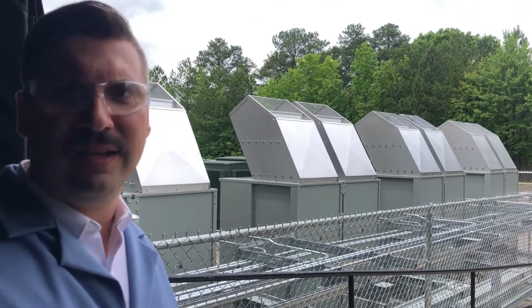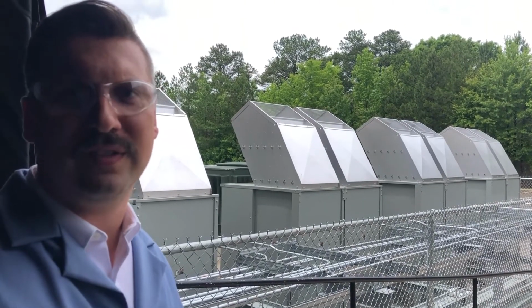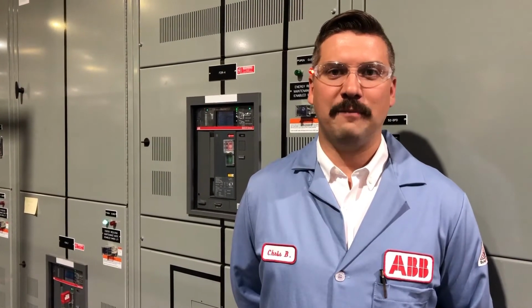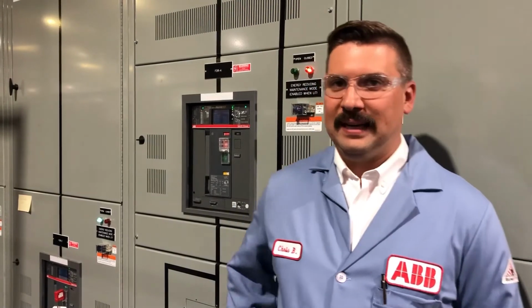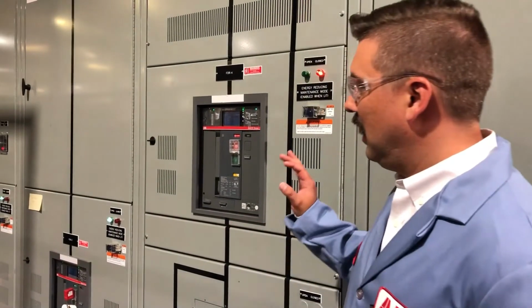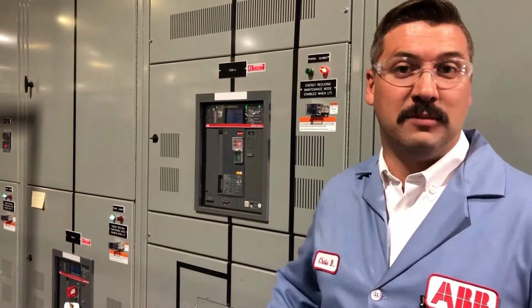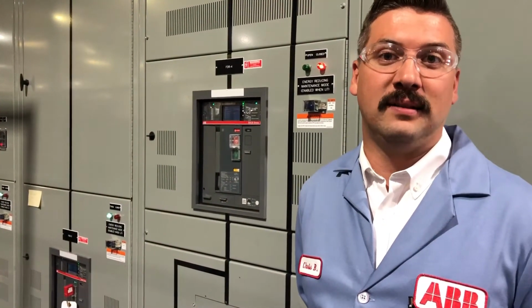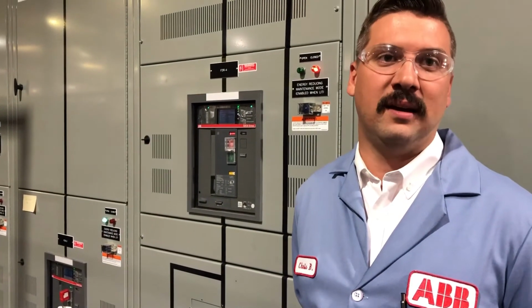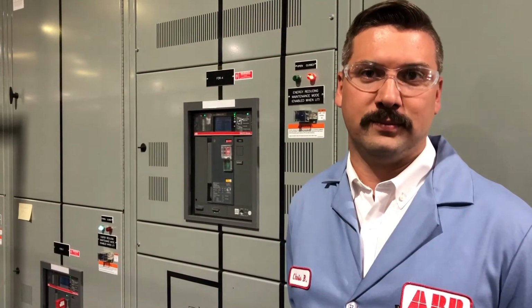Now we're going to transition and look at our main service entry here. Now we're at our 4,000 amp main service entry switchgear. We specifically designed this switchgear to support the 5 megawatt customer witness test center. It has all ABB Emax 2 breakers in it, and it builds in a lot of flexibility for us to expand and develop additional testing infrastructure in the future.